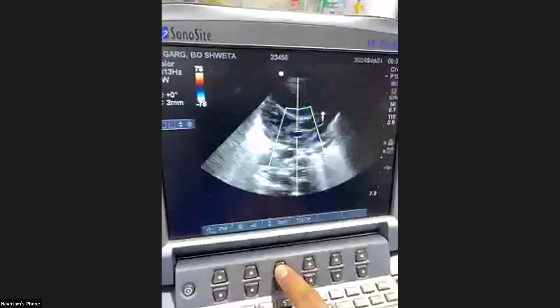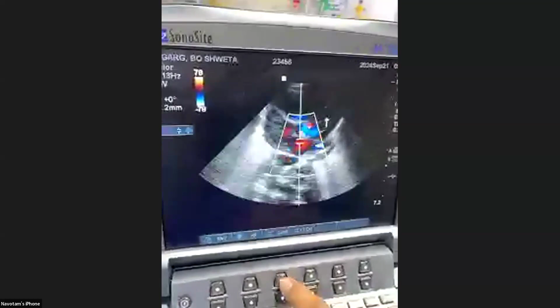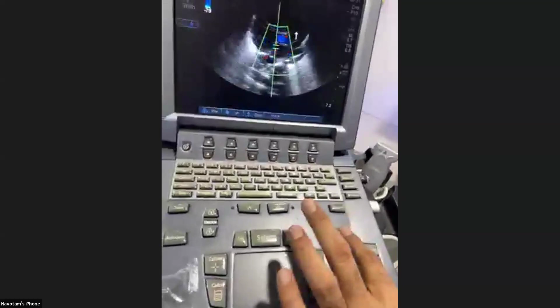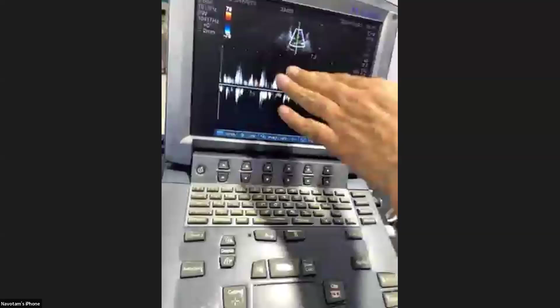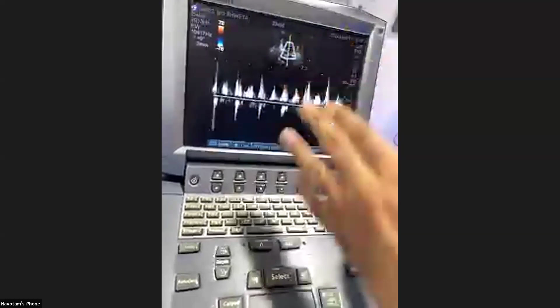And you can increase or decrease the depth of this range gate. So this is 5, 6, 7. Maximum 7 I can change if I have a bigger diameter to measure, and if it's smaller, then the minimum is 1. Fine. Now if I press the button update, what will happen on the screen is a Doppler which is coming, with a baseline, up and below. Up means towards the probe, and below means away from the probe. I'm not showing you what is seen, but this is how it will be shown on the screen.